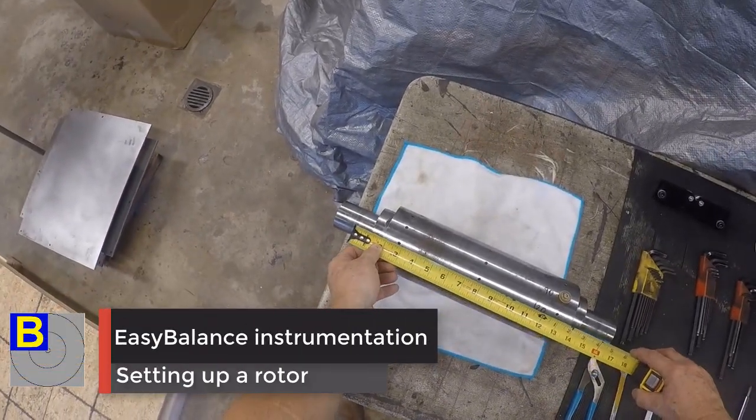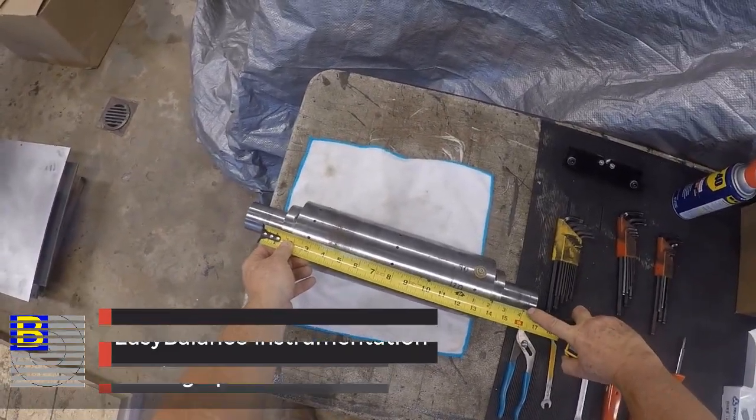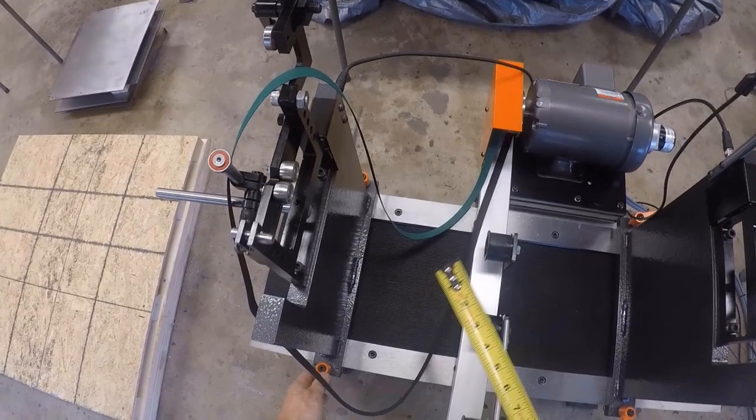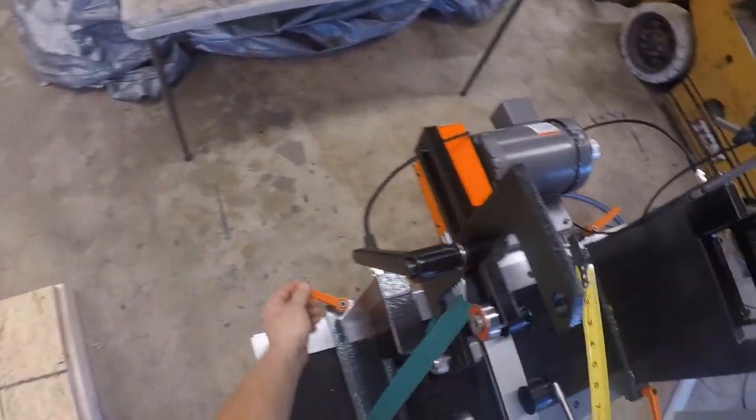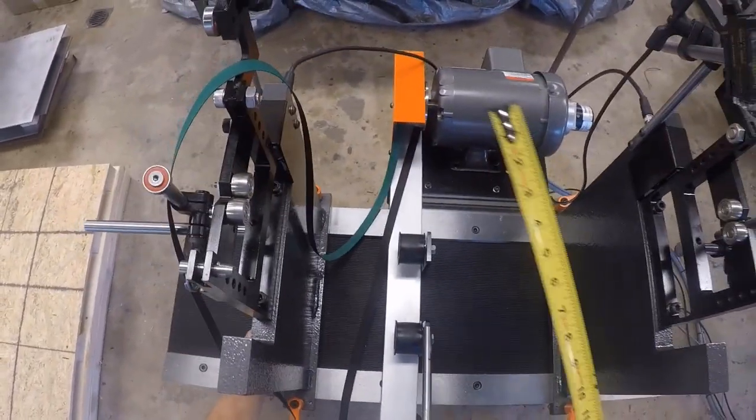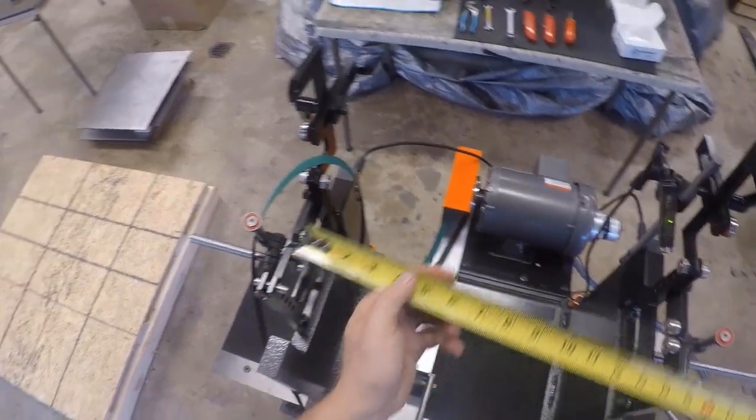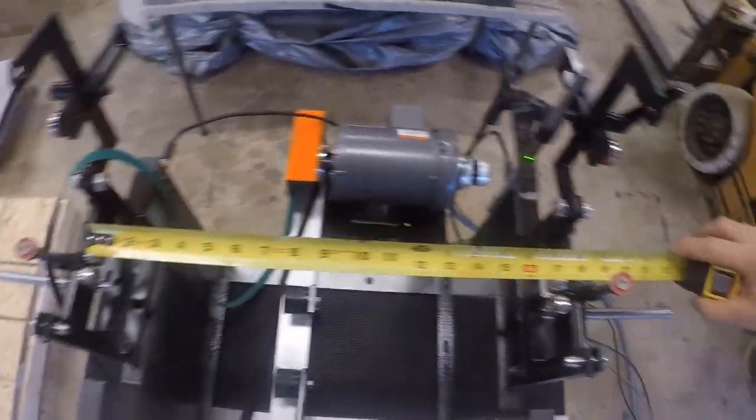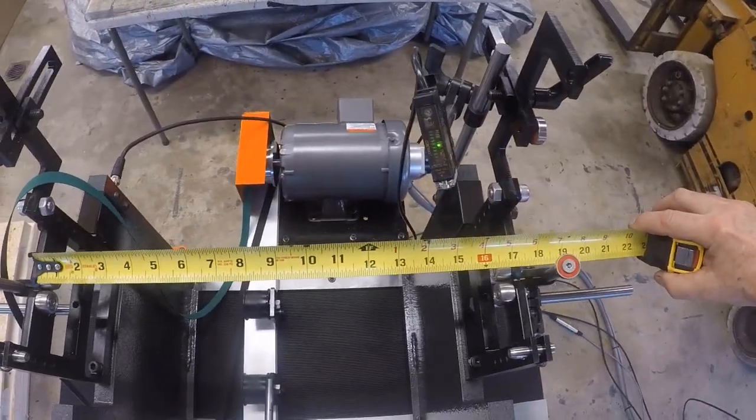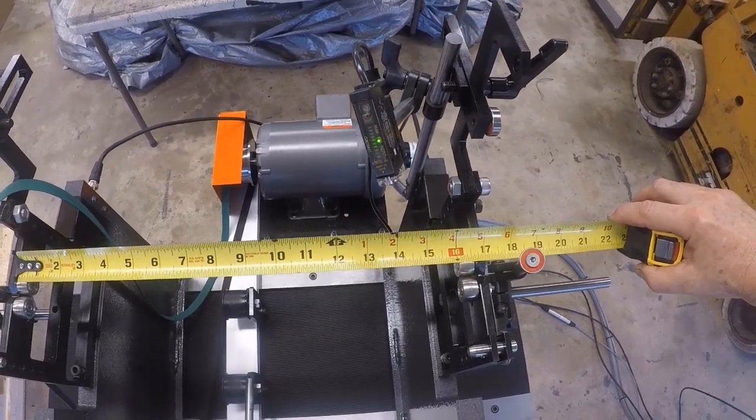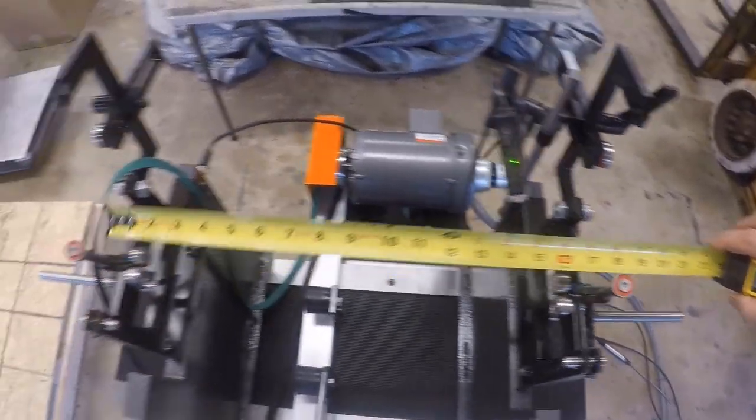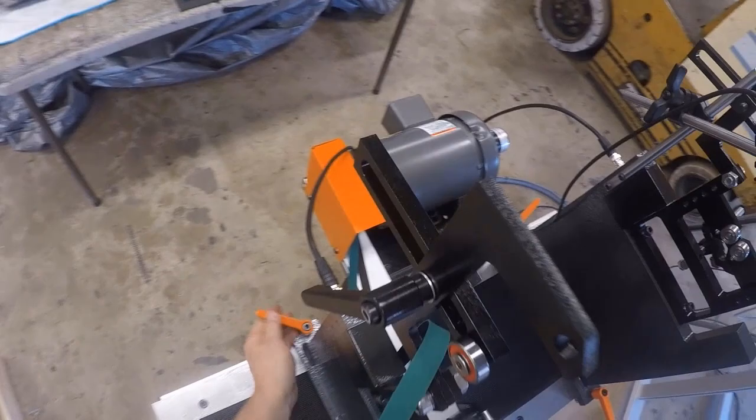First things first, we are going to measure the length of the rotor from one journal to the other, and we are going to adjust the two pedestals so that this machine can accommodate that rotor. We measured 16 inches in this case, so we need to adjust the pedestals to this total length of 16 inches and then we lock them down.